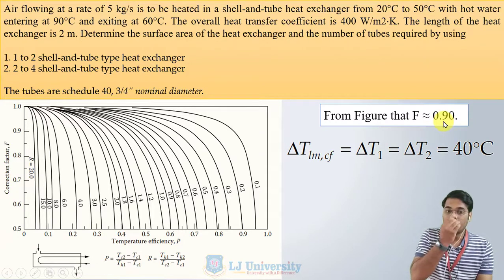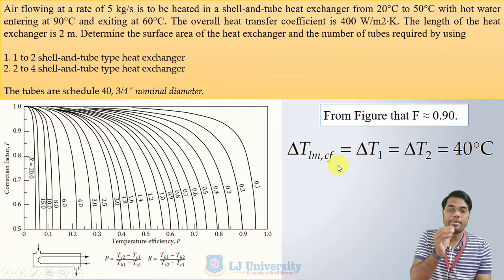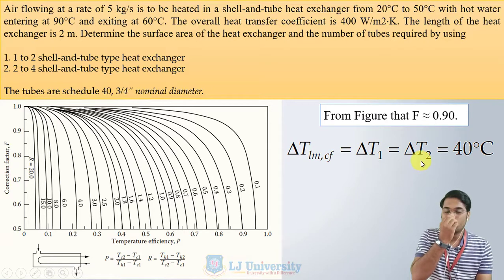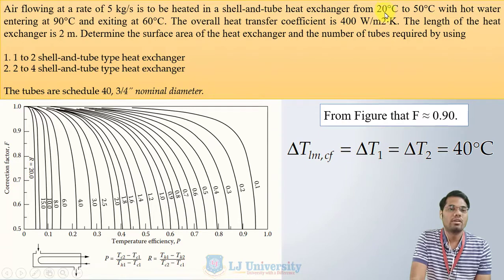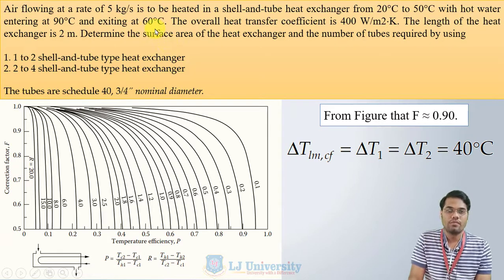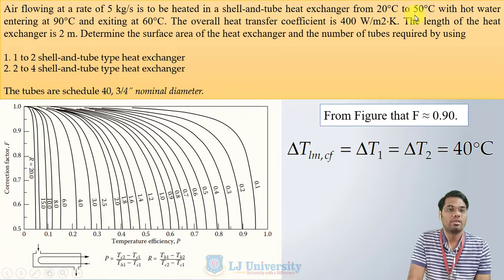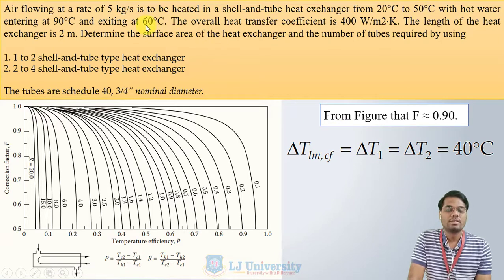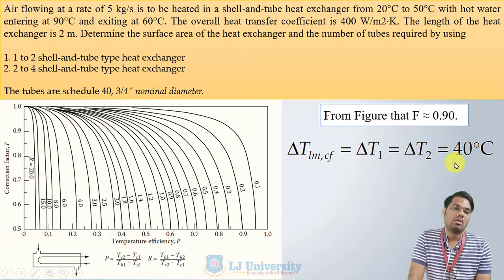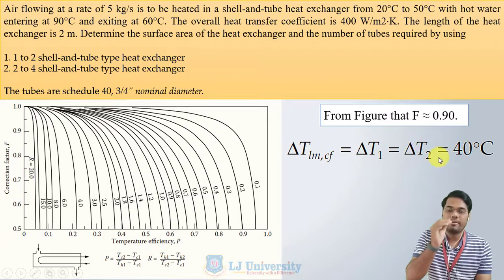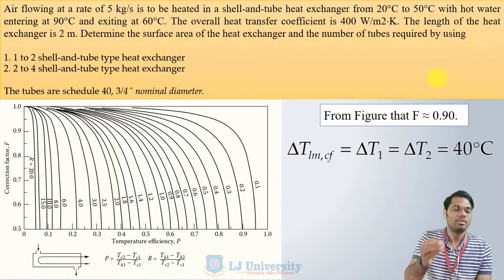This is a special case where the LMTD equals either ΔT1 or ΔT2. Here TC1 = 20°C, TC2 = 50°C, TH1 = 90°C, TH2 = 60°C. ΔT1 = TH1 − TC2 = 90 − 50 = 40°C, and ΔT2 = TH2 − TC1 = 60 − 20 = 40°C. Since ΔT1 = ΔT2, the LMTD for the counter-flow arrangement equals 40°C directly.